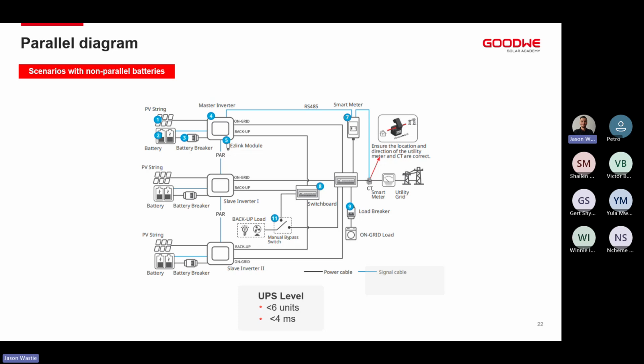A second way that we can do this is using non-parallel batteries, and this is when we have got a site that is maybe a year or two old and they need to increase their battery capacity, but we can't necessarily just add new batteries onto old batteries because of the SOC deficits, or SOH deficits, that we'll have. We can add a second inverter and different batteries onto that inverter. So on battery inverter number 1, we could have the GoodWe Lynx AG3 batteries, and on inverter number 2, we can connect BYD batteries, inverter number 3, Parlantech batteries.